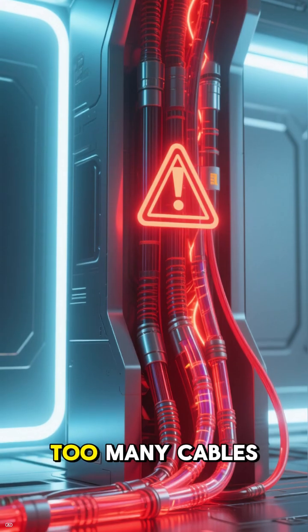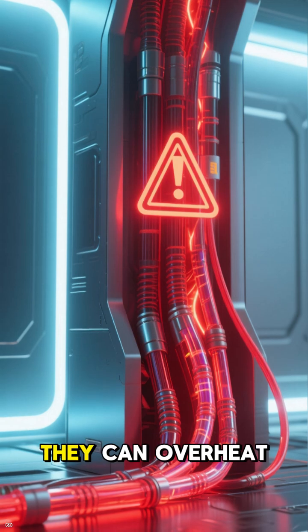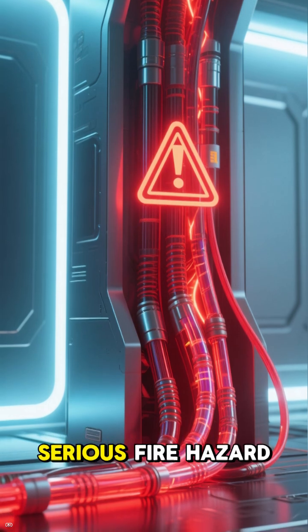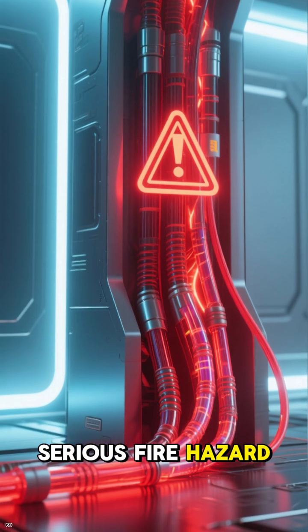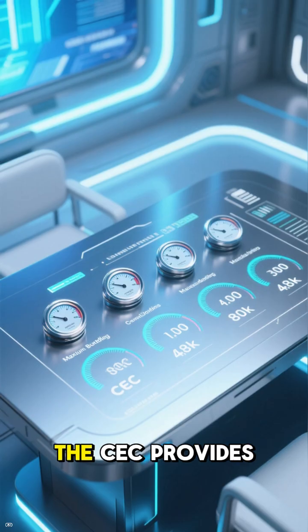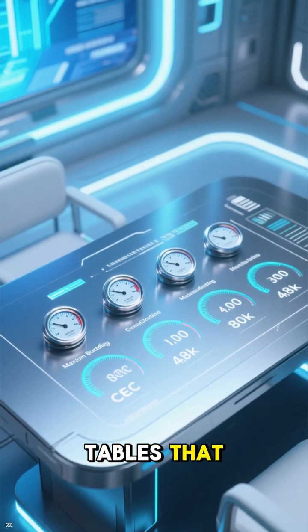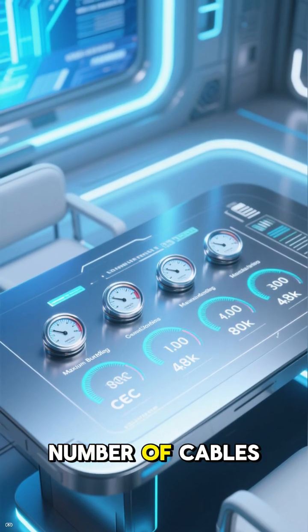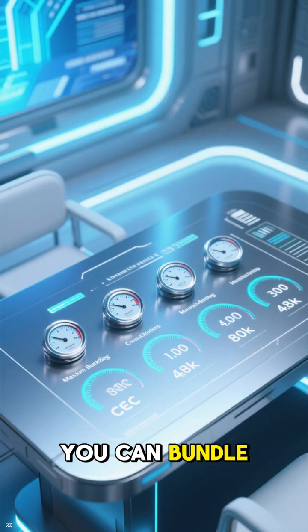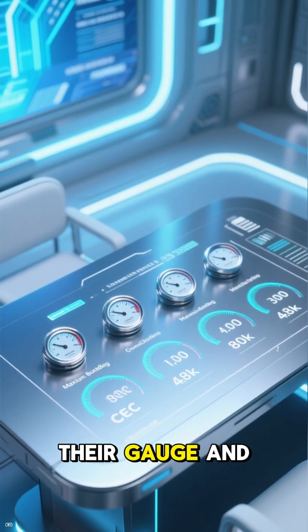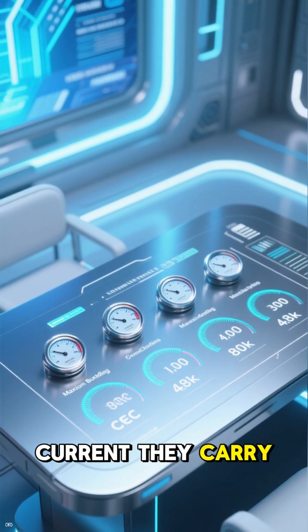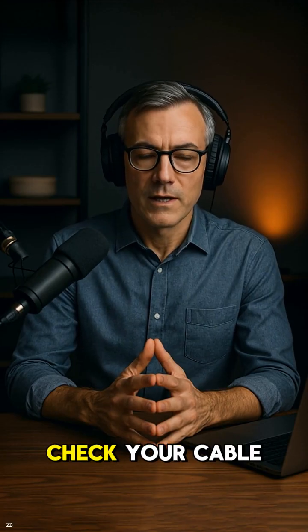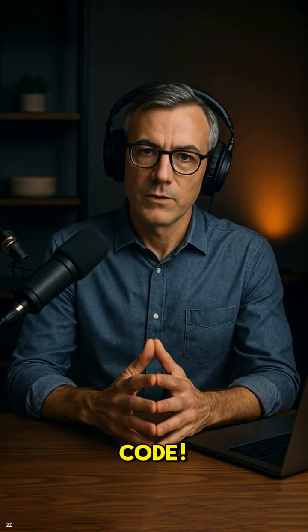If you bundle too many cables together, they can overheat, which is a serious fire hazard. To prevent this, the CEC provides tables that specify the maximum number of cables you can bundle together based on their gauge and the current they carry. So, always check your cable specs and the code.